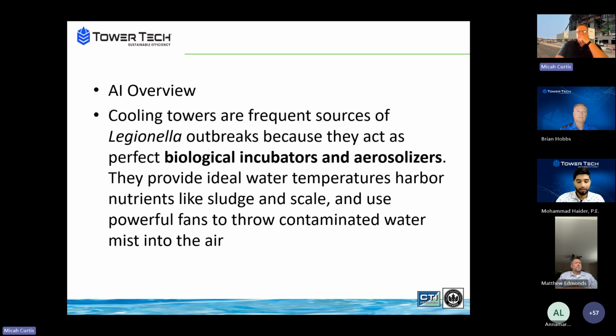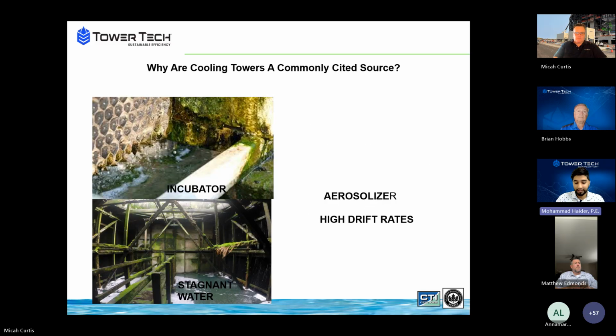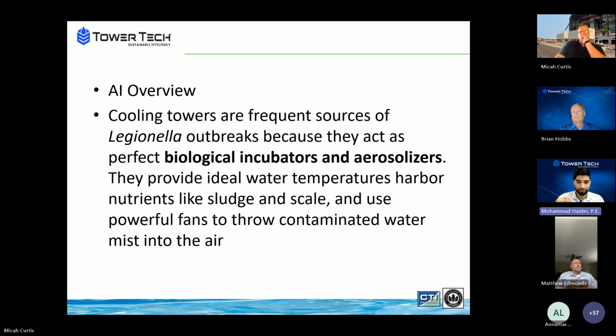Why cooling towers? Yeah, so cooling towers are considered a frequent source of Legionella outbreaks because they're considered to be biological incubators in the traditional sense of the word. As we discussed on operating temperatures, cooling towers typically operate with a warm water temperature of about 85 to 100 degrees and a cold water temperature of about 70 to 85 degrees, which overlaps almost exactly with the optimal growth range of Legionella, interestingly enough. So the tower is intentionally maintained in the biological sweet spot for Legionella growth. And that's why we consider them biological incubators and aerosolizers, in the sense that they create drift, which we're going to discuss later. Okay. All right.